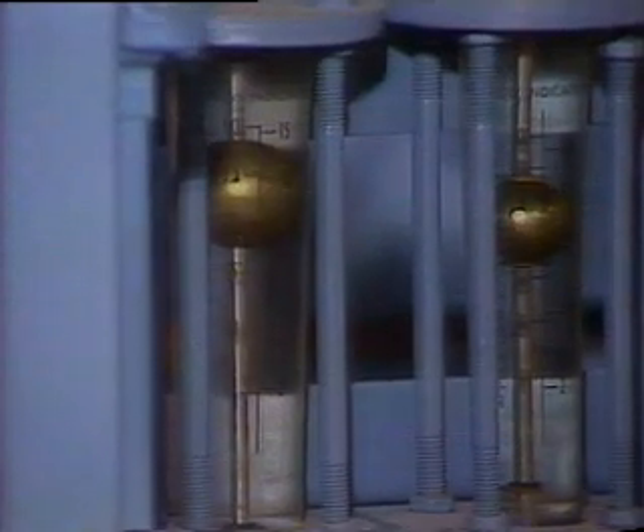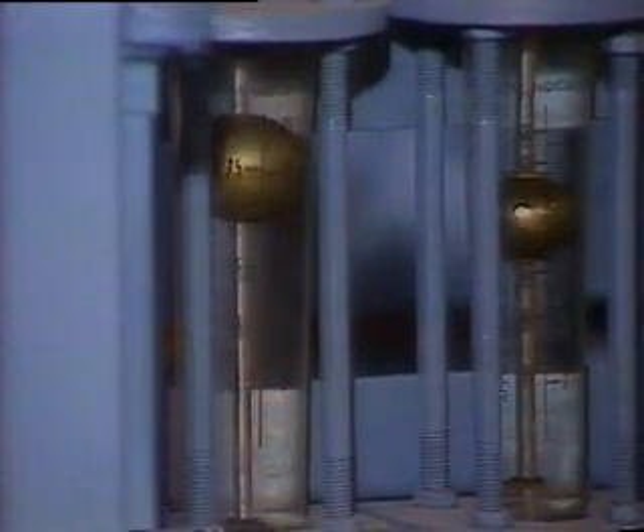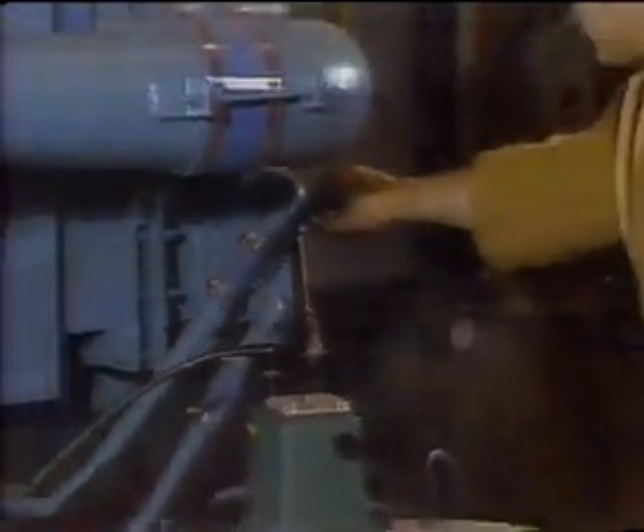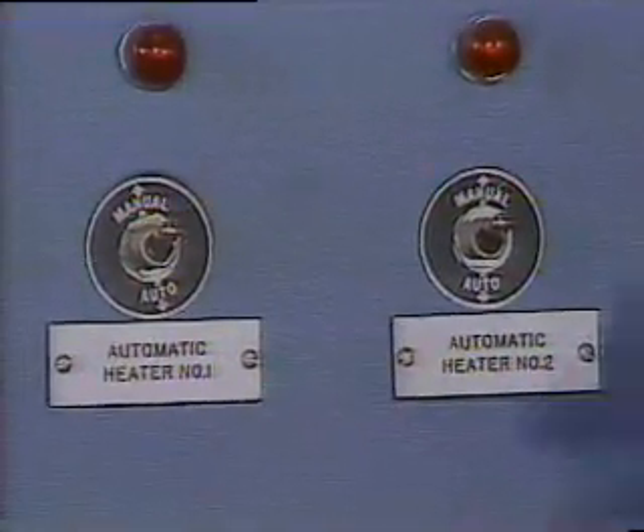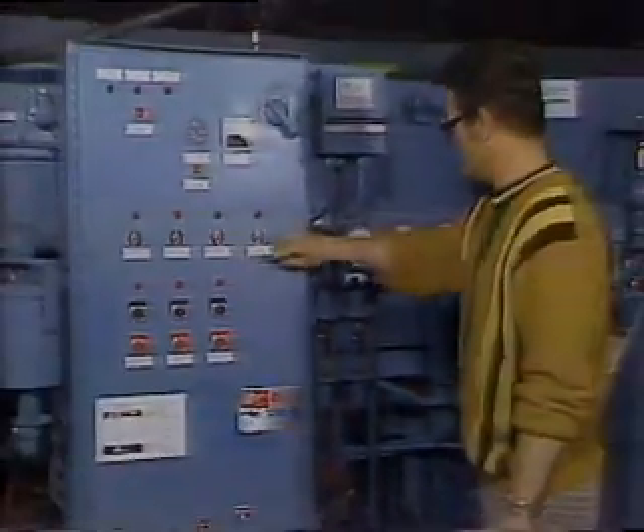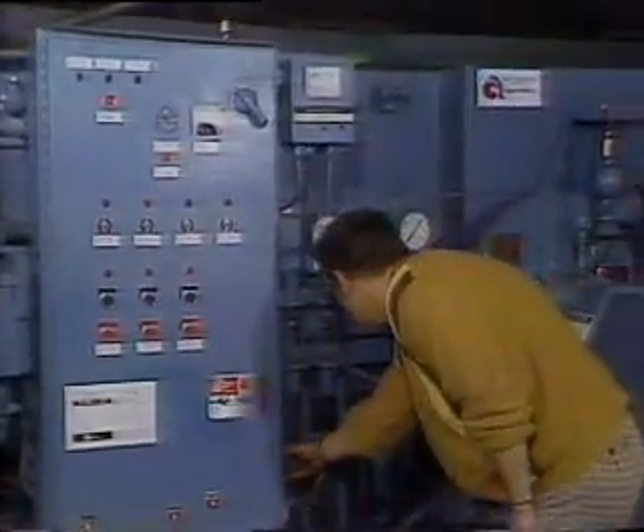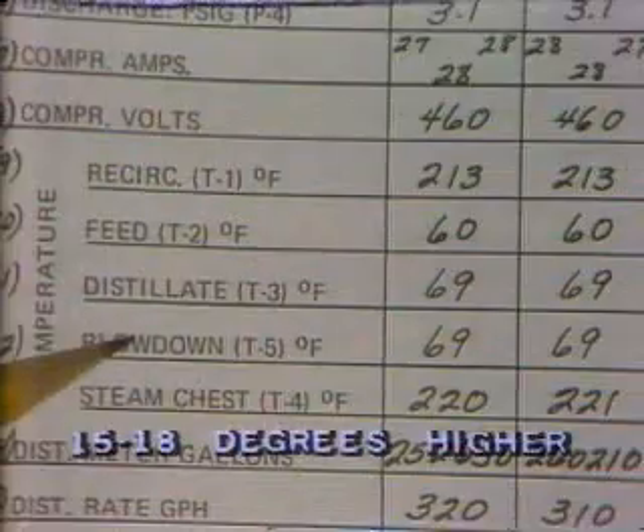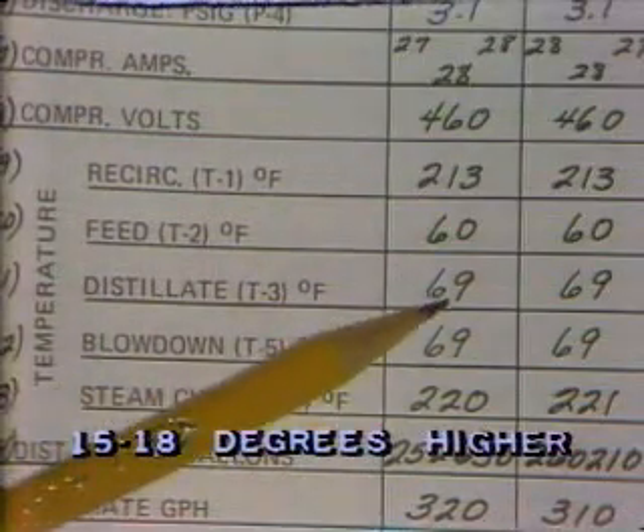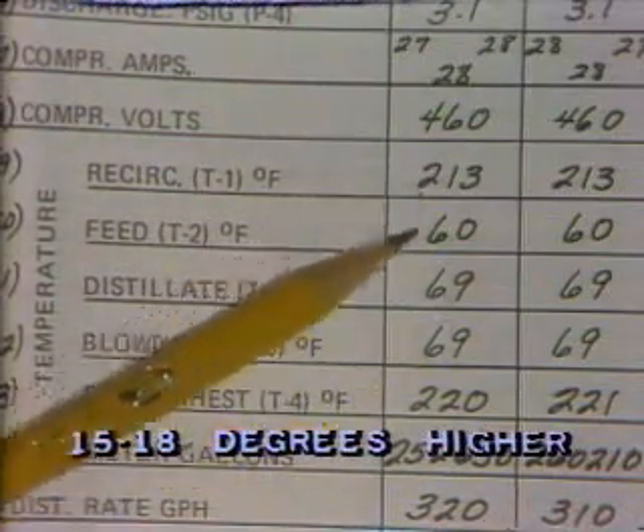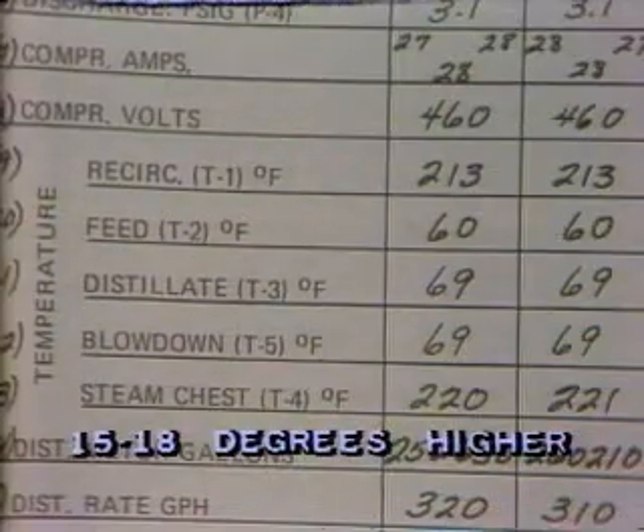If your heater correction doesn't seem to make a difference, make sure that your feed water rate is correct, steam chest vent valve is set for just a wisp, all electric heaters are turned on and operating properly, the recirc pump flushing water is about a quarter of a turn open, and the distillate and blowdown outlet temperatures are not more than 15 to 18 degrees Fahrenheit higher than the inlet temperature. This last check will tell you whether or not the heat exchanger is scaled over.